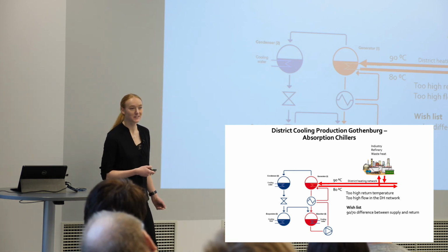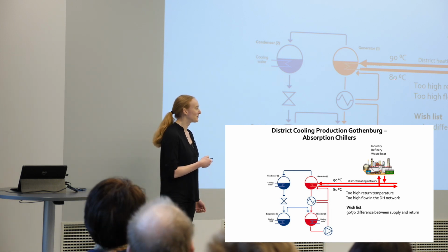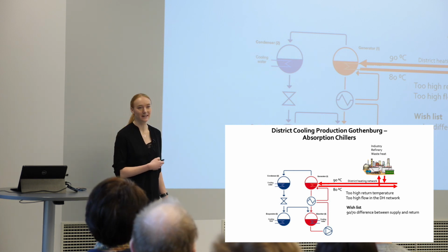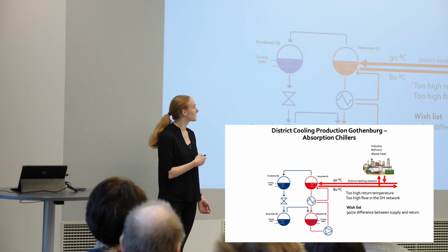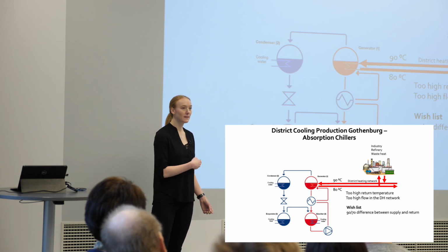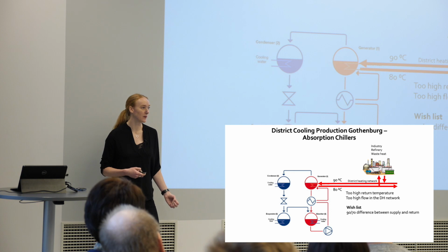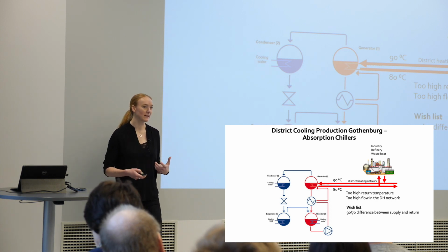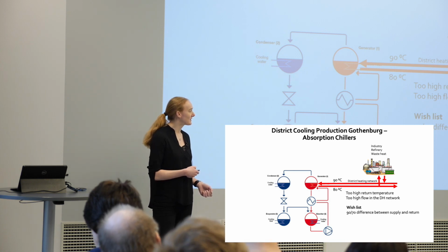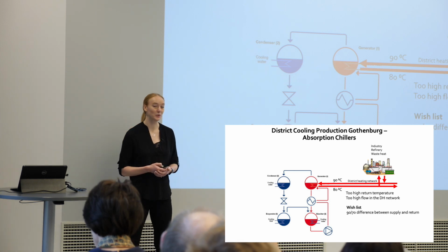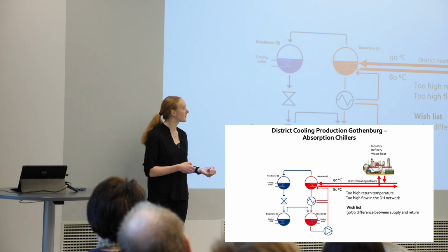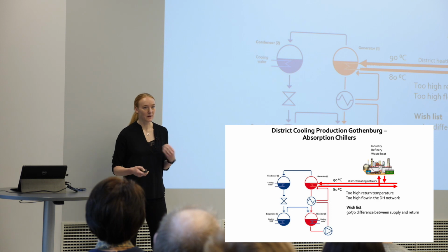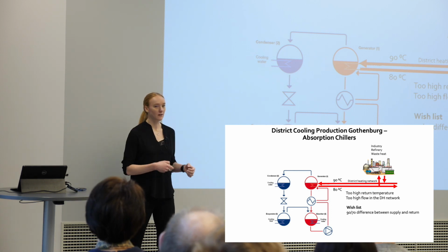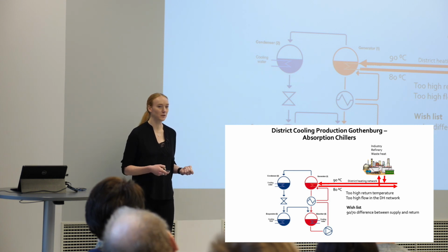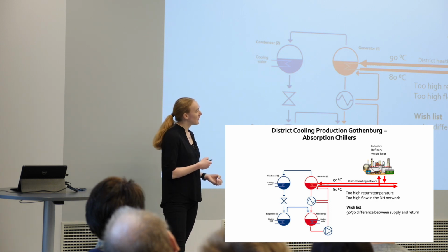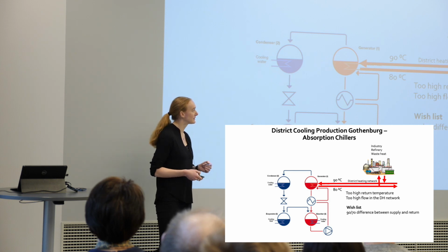And this creates some problems with the district heating system. The return temperature is way too high for the district heating system. And it also leads to a very high flow rate through these absorption chillers because of this low delta T. And this was something that Gothenburg Energy did not think of when they ordered these Broad and York machines when the system was under development. So today on the wish list is at least a 20 delta T in the generator of the absorption chillers. So they're looking into ways of either replacing the current heat exchanger in the generator, or maybe they have to actually replace the chillers, because right now they cannot invest in more absorption chillers in Gothenburg district cooling system, because it's maxed out the amount of district heating water that can be used in them because of this low delta T that the chillers have.